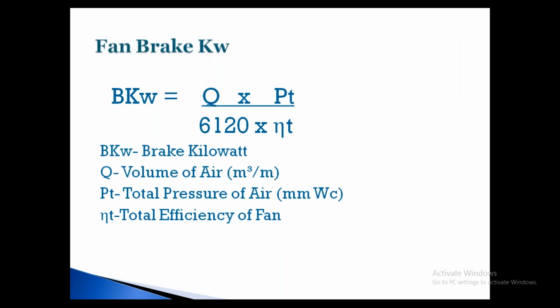In our textile industry in India, there are a lot of mills which are running with old propeller type impellers, 4 blade, and low efficiency fans, and motors also. Whenever they want to save energy, they immediately go for a high efficiency motor and fix the motor first, whichever is the easiest way. But what about the fan? That will be working at 55%, 60% efficiency. Again, there is no point; your power will be more. So if you retrofit the fan with a high efficiency fan, you will really save energy.